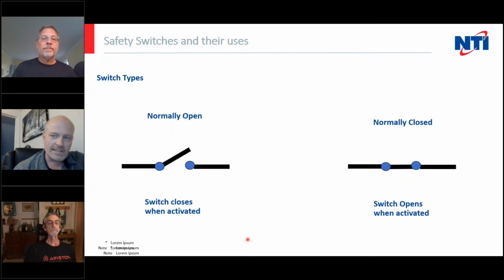Okay, so now we've gone over the basics of how the boiler decides to fire. We're going to go through some basics on switches, and some of this is a bit simplistic. I hope for you guys there's some value in it, but there are 2 common types of switches: normally open and normally closed. Each switch is shown in its normal state, meaning when you're sitting there and you haven't provided the conditions that should trigger it, whether that's a low water cutoff, an air switch, a pressure switch, whatever it happens to be. This is the state that the switch sits in when you set it on the desk in front of you. So normally open means the contacts are not connecting a circuit, and normally closed is just the opposite.